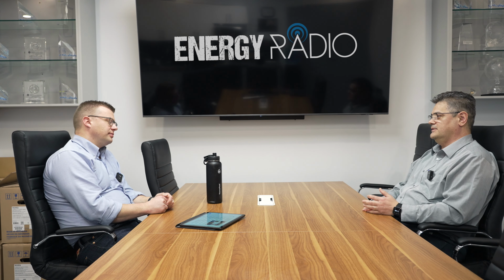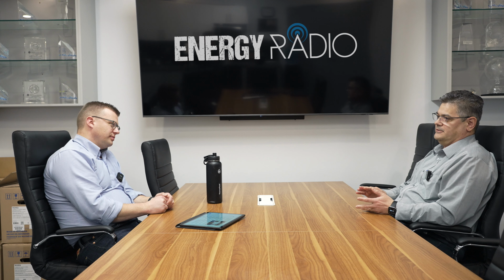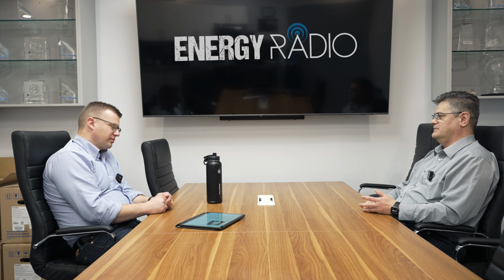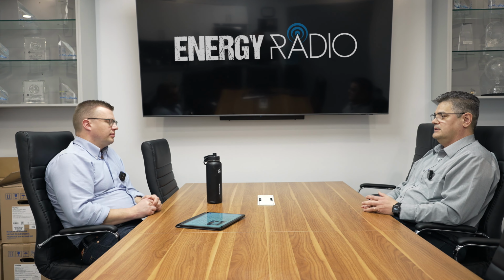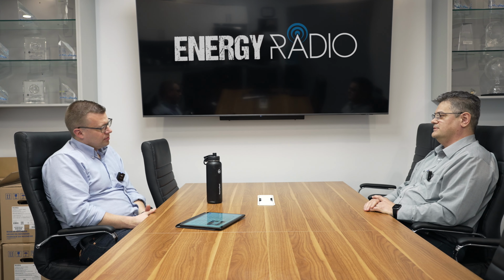That was the dreaded February 15, 2015, when a chain of unfortunate events led to a plant shutdown and a total freeze-up of the plant. It was a combination of a power failure and a curtailment process in progress from Enbridge. We are an interruptible customer for our boiler for steam production, and that means in winter time, when the pressure in the system drops, Enbridge has the option to call us and ask us to get off the gas network.